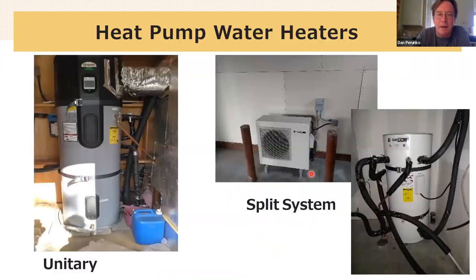Let's see, I did that. And so, okay, here are our heat pump examples. On the left is a unitary system. And so the tank is there. The water to refrigerant heating coil is here. The refrigerant to air heating coil is up here. And there's a compressor and valves and things in there. And this particular unit is in a confined space, right? This room is too small for the amount of air the machine needs; it doesn't contain enough air for the machine to be able to absorb enough heat.